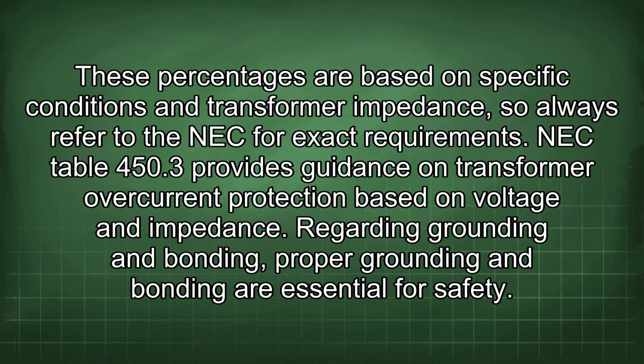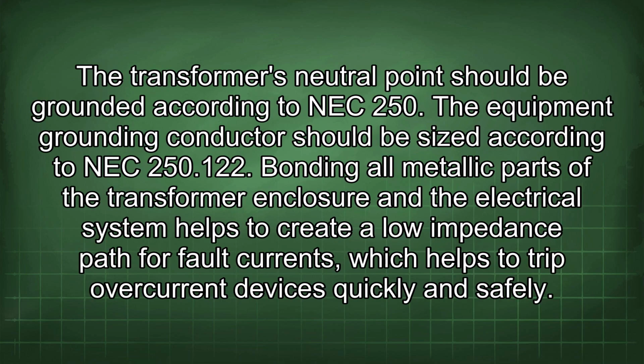Regarding grounding and bonding, proper grounding and bonding are essential for safety. The transformer's neutral point should be grounded according to NEC 250. The equipment grounding conductor should be sized according to NEC 250.122. Bonding all metallic parts of the transformer enclosure and the electrical system helps to create a low impedance path for fault currents, which helps to trip overcurrent devices quickly and safely.